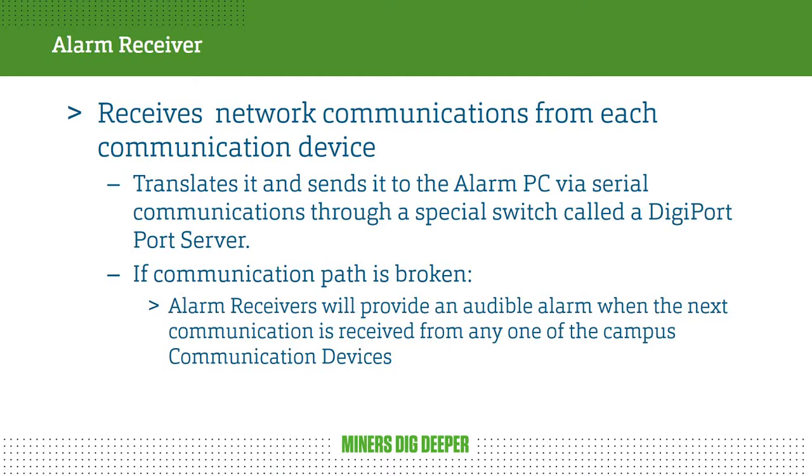If there was ever a problem with the port server or any communication in that part, the alarm receivers will still be able to receive the signals, but then they would not be able to pass them on, and then they will provide an audible alarm when the next communication is received from any of the campus communication devices. So if you ever hear that alarm beeping in one of those blue rack-mounted devices, that basically means I have a signal and I cannot pass it on to the PC.